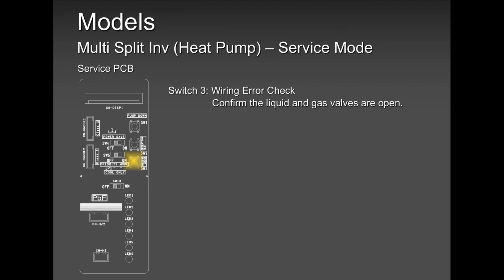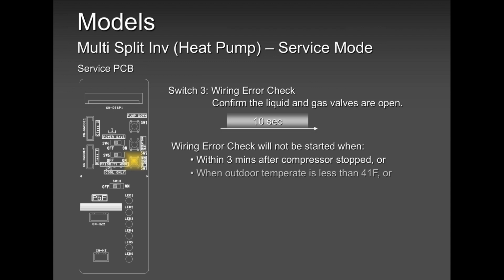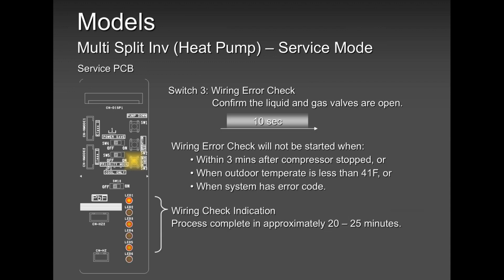This is what I don't want you to use, wiring error check. It kind of rectifies a minor error, but it may come back after maybe you change the PCB, or maybe there was a power outage for about 48 to 96 hours, or maybe you switched off the unit on a vacation trip and when you came back, you turned it on. Everything that is in a service PCB on the wiring side got erased. So please don't use this option, even though it's there. It is just going to waste your time and energy, honestly.